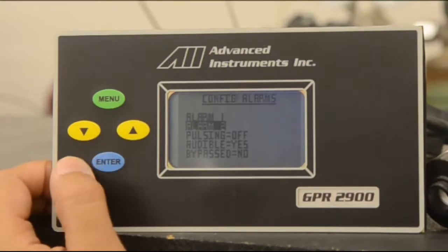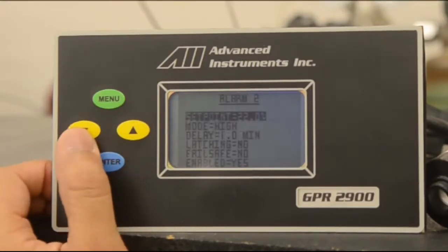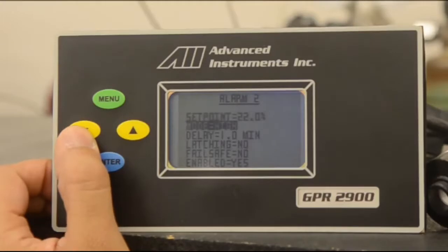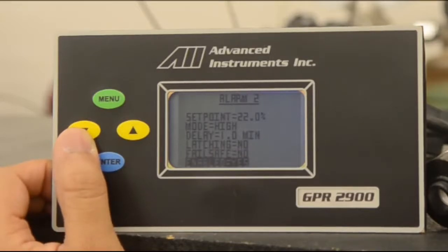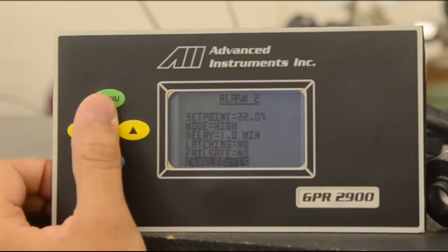If you scroll down to alarm 2 and press enter, you have all the options as alarm 1, and you can set your alarm mode to either high or low, delay, latching, fail-safe, and enabled. These are all user configurable and up to your process to determine what is the best levels for your application.